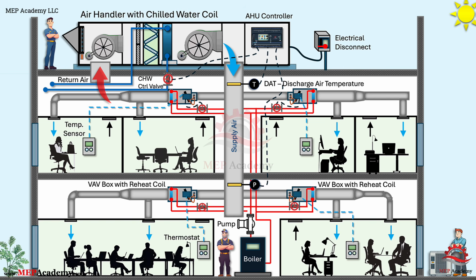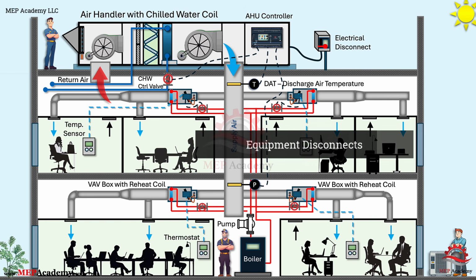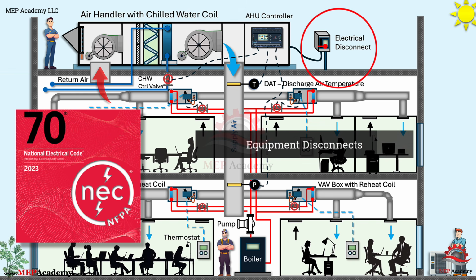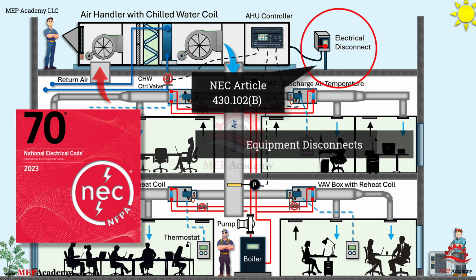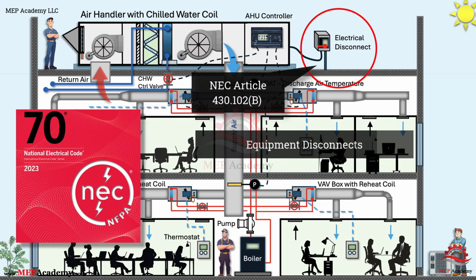The second common coordination issue involves equipment disconnect switches. The National Electrical Code requires a disconnecting means within sight of motor-driven equipment. NEC Article 430.102(B) requires a disconnecting means located within sight from the motor and driven machinery location. Mechanical equipment such as rooftop units, exhaust fans, and air handlers therefore require local disconnects. The conflict occurs because mechanical drawings show the equipment, while electrical drawings may only show feeders or panel connections. Mechanical contractors often assume the electrical contractor includes the disconnect because it is an electrical device. Electrical contractors may assume it is excluded if it is not specifically shown.